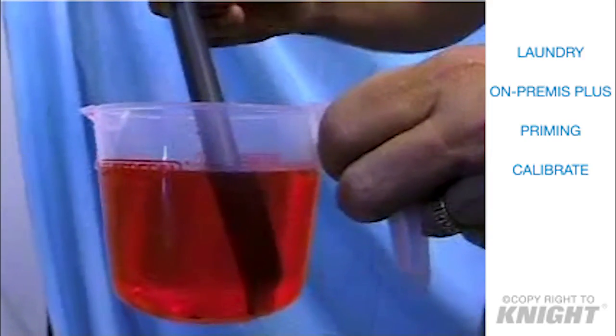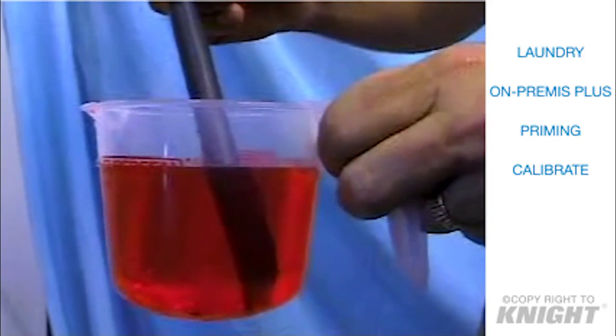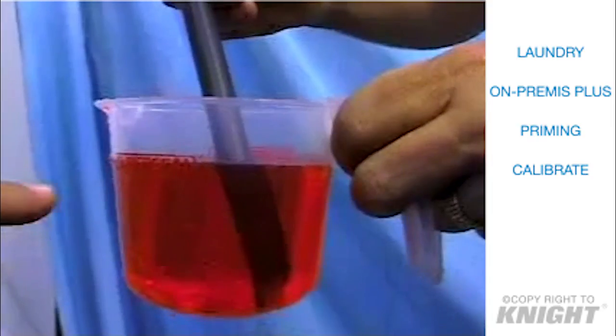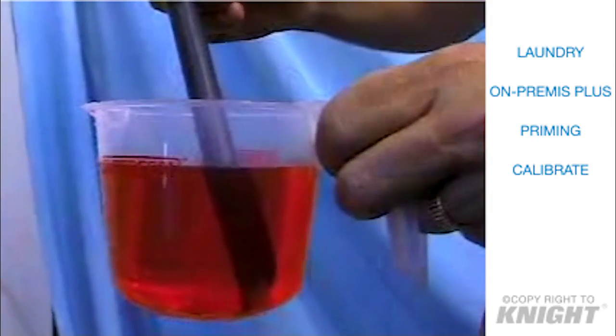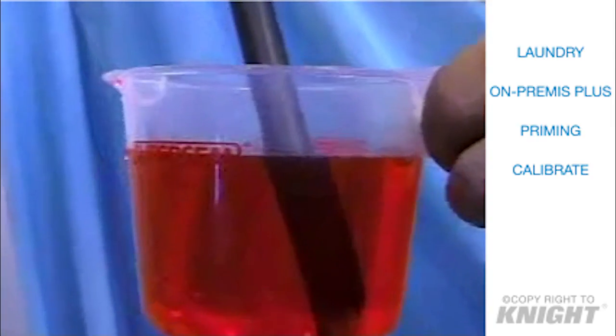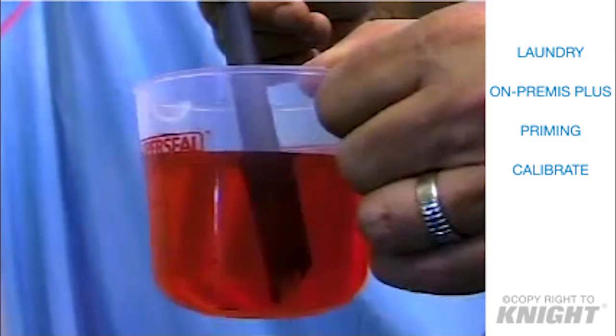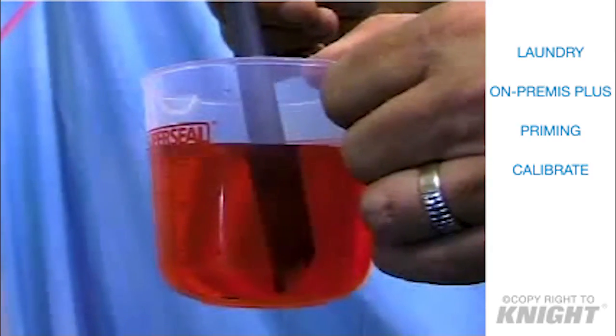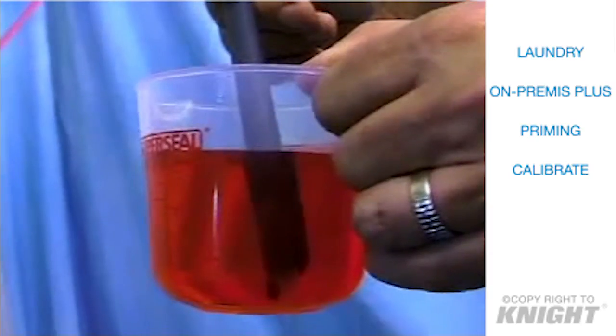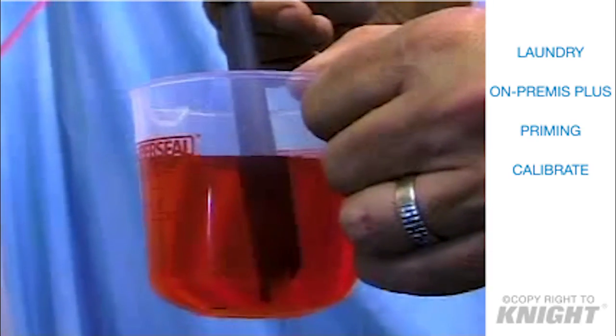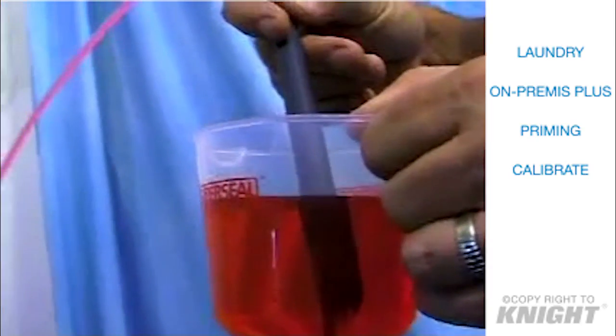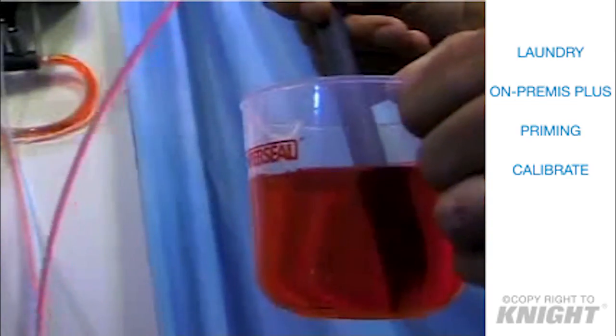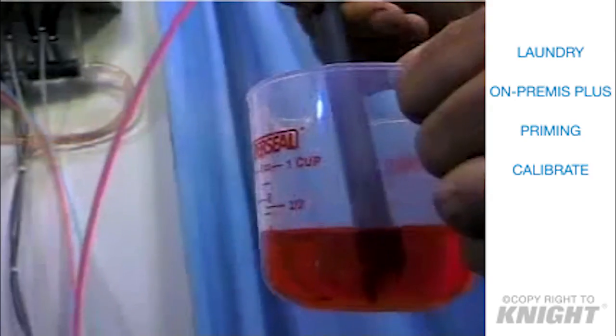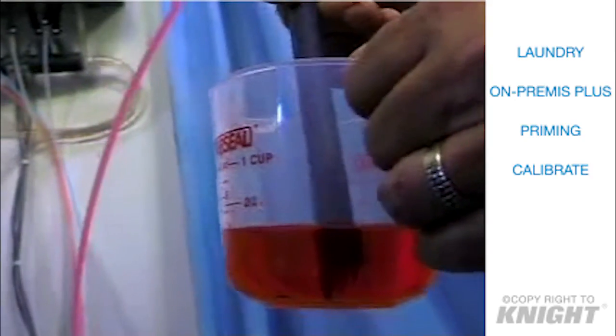What I'm going to do first is get us to the first graduation point, which would be the 8-ounce mark here. That'll be our starting point. In order to get the most accurate calibration, I've also selected our flush pump output to run simultaneously as our peristaltic pump runs. This way we also account for the water pressure running through the manifold. Okay, our chemical pump has run for 30 seconds. Now let's check and see how much we drew off.